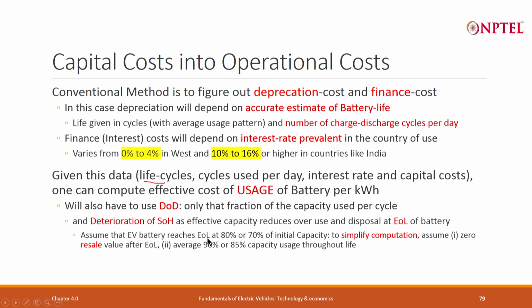We will assume two things to simplify the calculation, though one can do a more detailed calculation. Let us say end of life is at 80% or 70%, we will choose one of them, multiply it by the depth of discharge, say 90% or 85%, and take the average of that value when new and when nearly at end of life, and use that as the per-cycle value.